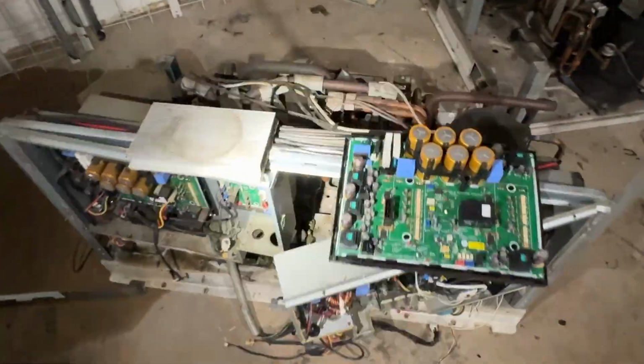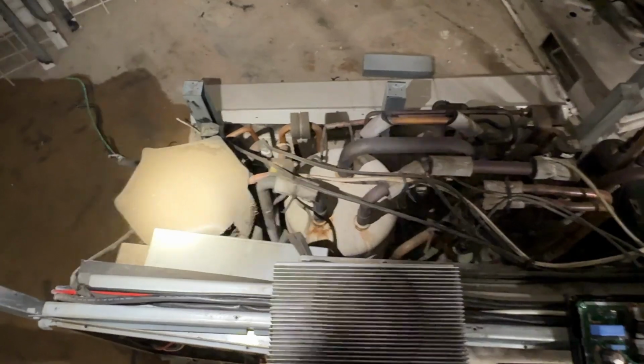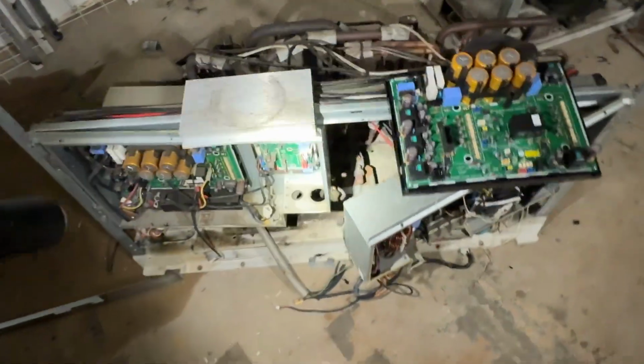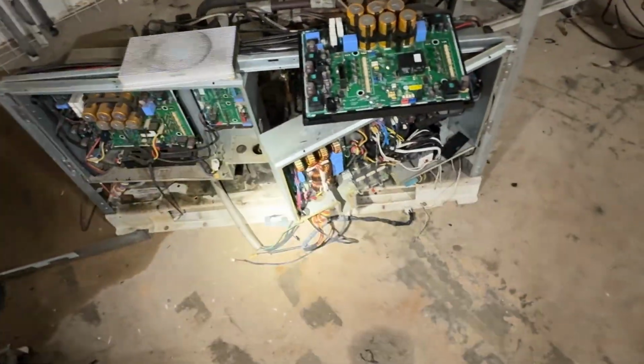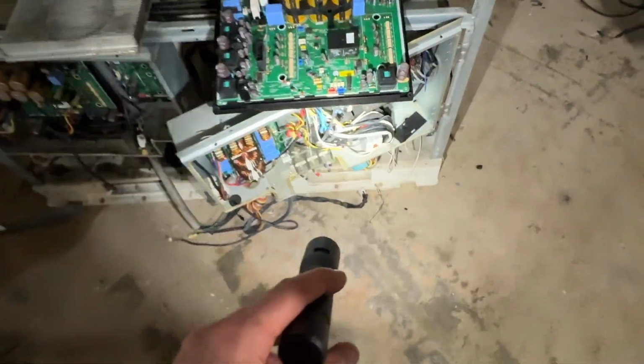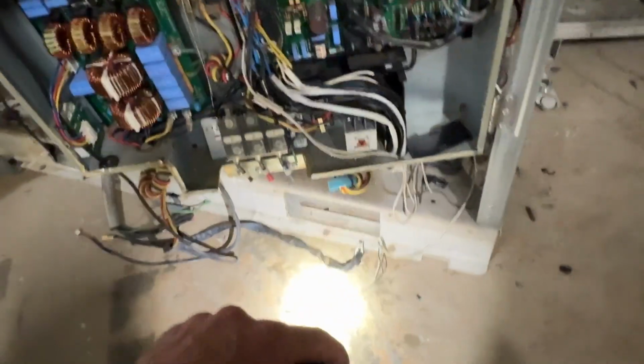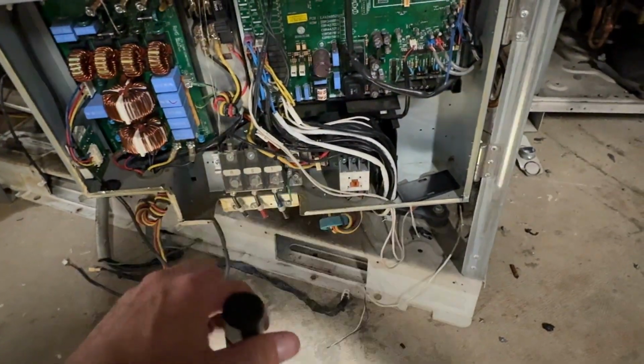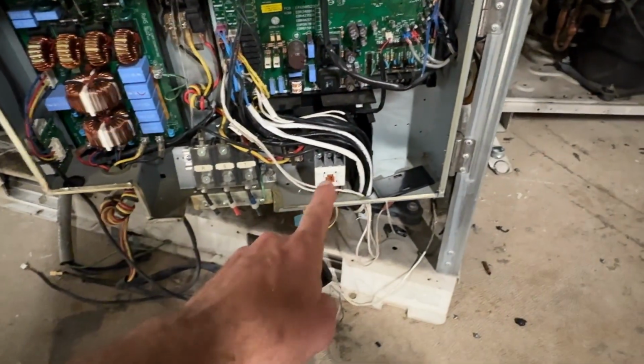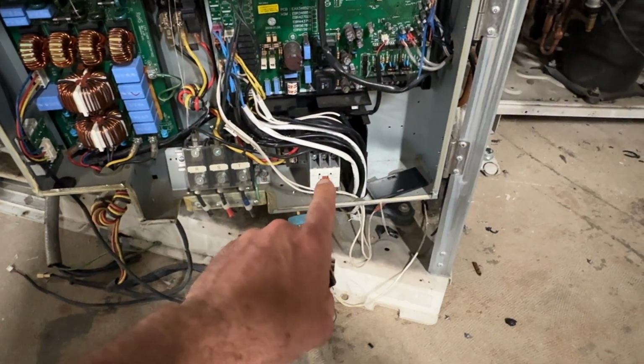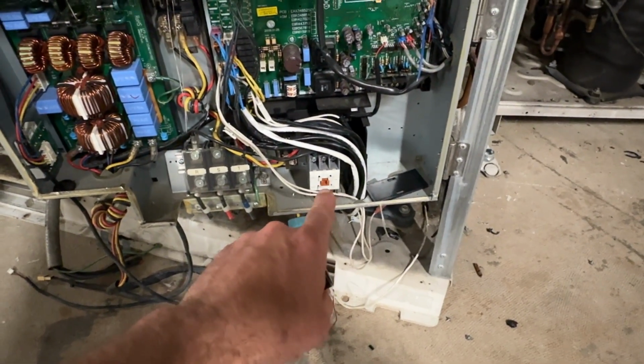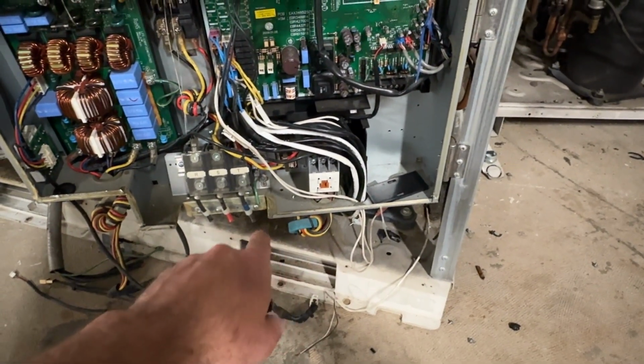In these units, there are two compressors. This is the inverter and this is the standard. If you ever walk up on any style of VRF unit and want to know which is which—a lot of the newer ones have two inverters, but if you see a contactor, then you know you've got a standard. You can also look at the wiring diagram.